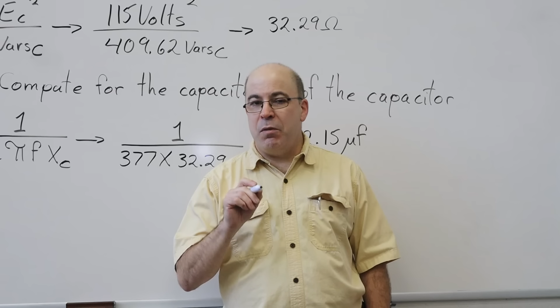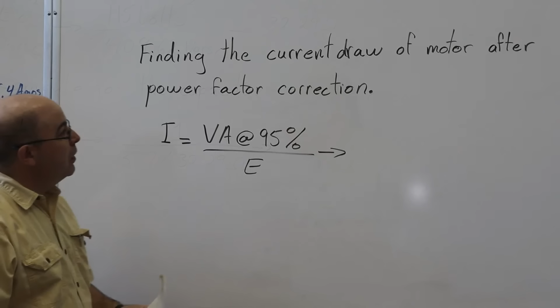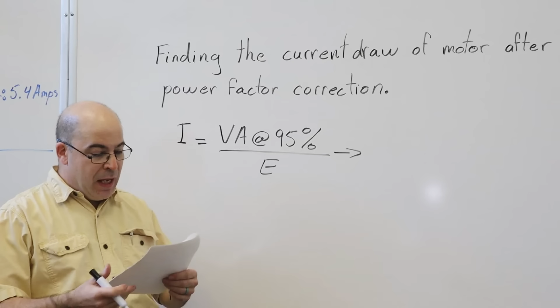It would be nice to know, after I've done the power factor correction, how much current I would have eliminated from my power supply. So I've got one little calculation to do. As a supplement to the calculations we've just done on power factor correction, I was curious to see how much current I could have gotten rid of once I've done my power factor correction. So when I install the capacitor I have just calculated and sized, what kind of current am I going to see being drawn from the system?